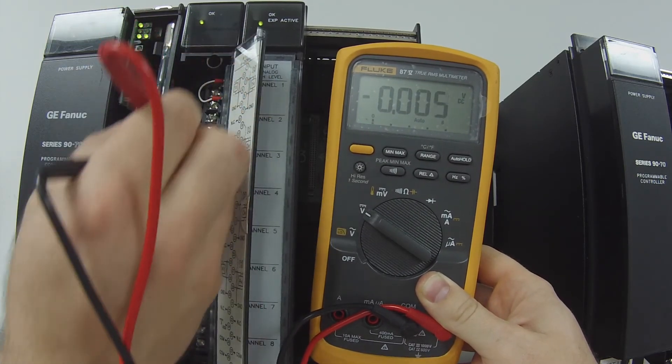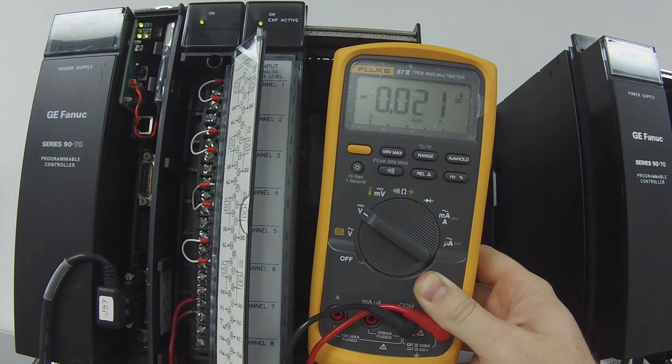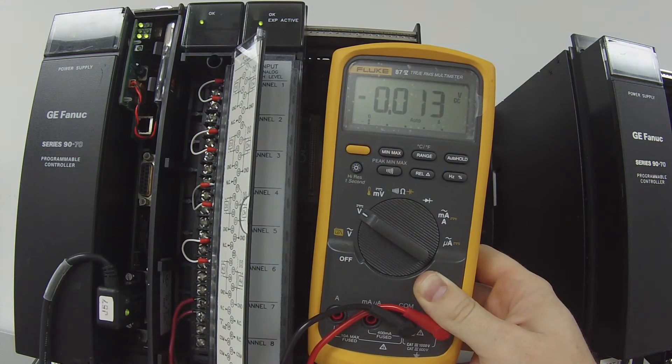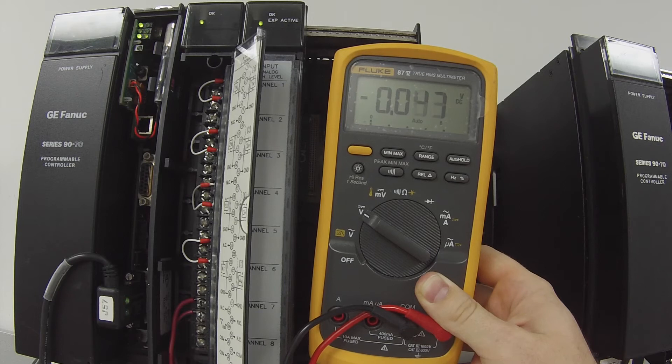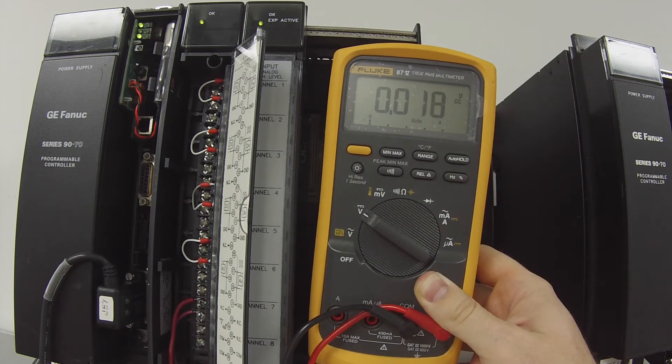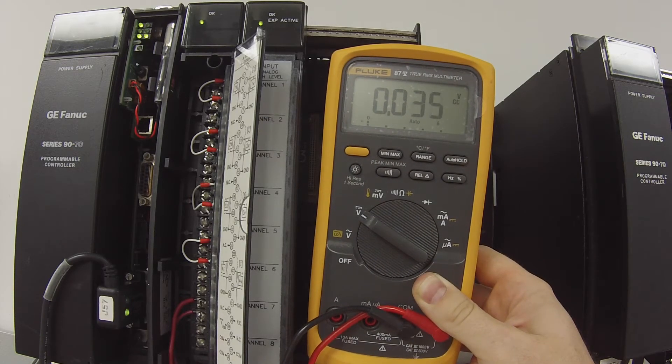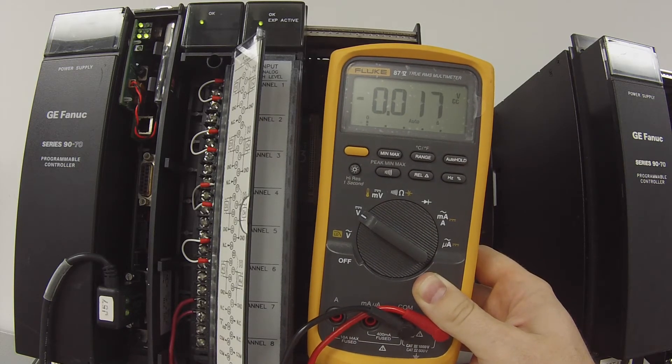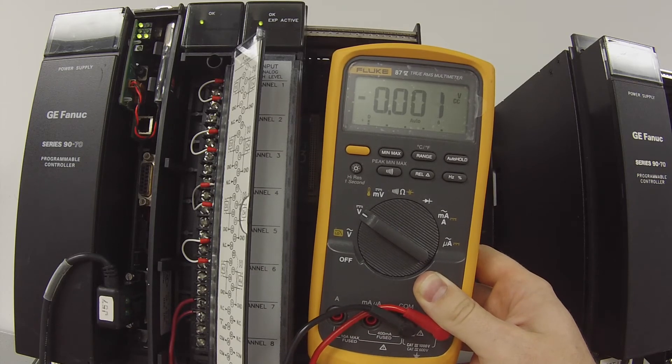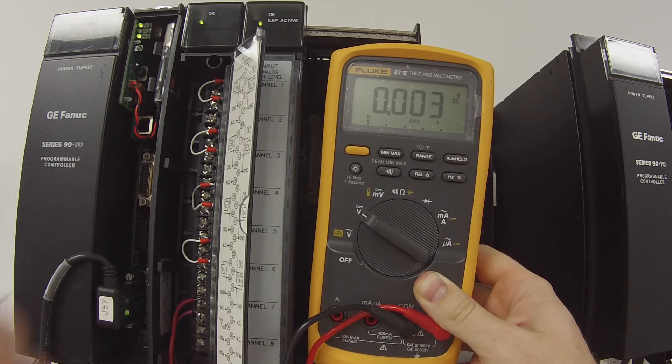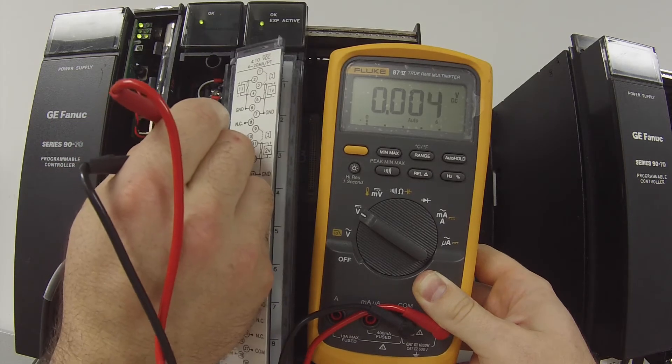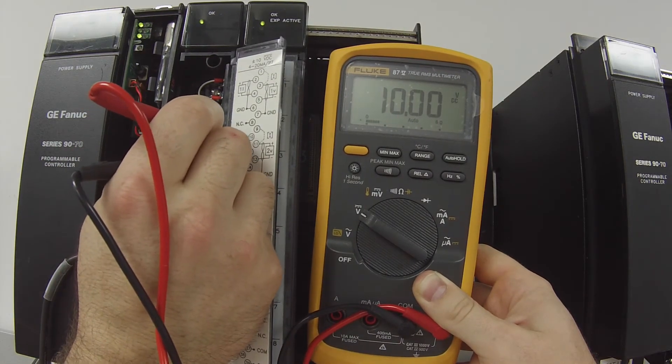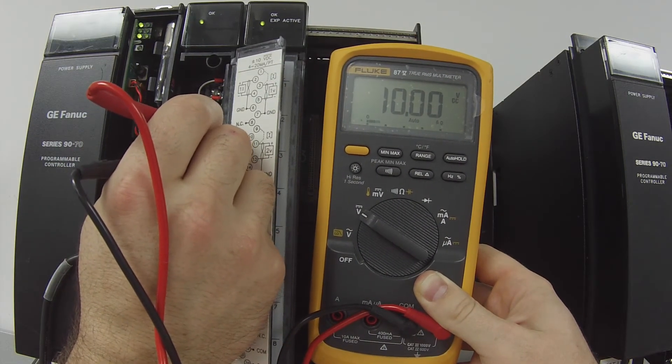The reason I do that is because if the channel has failed it would still read 32,000. They usually fail at full value or at partial value. Now I'm going to work my way to number 2. Same thing, I'm going to zero it out.